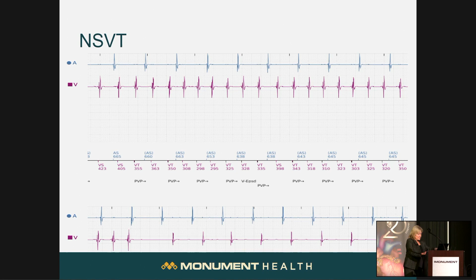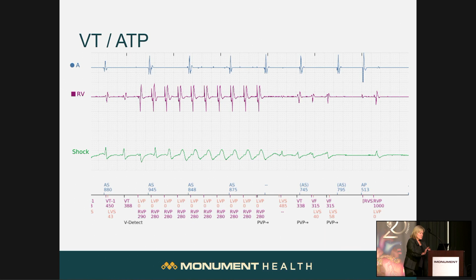On this one, it's sensed VT and delivered a burst of ATP where the defibrillator paces 10 beats at a fast rate to terminate the VT. Unfortunately, he continued to have more therapies, and one of the things I like to look at is the arrhythmia logbook, which you see a part of it on the top there.